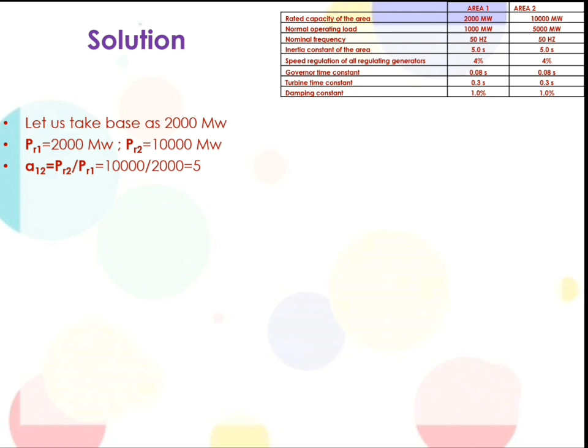Now as we did in the single area system, let's determine the value for B1 as well as B2. B1 is equal to dou PD1 divided by dou F. So here also we consider that for 1% change in load, the change in frequency is 1%. So 1 by 100 into 1000 divided by 1 by 100 into 50, so 20 megawatt per hertz. Now as we know that it has to be in the unit per unit megawatt per hertz, it is being divided by the rated capacity or the base 2000 megawatt. 20 divided by 2000, which is equal to 0.01 per unit megawatt per hertz.